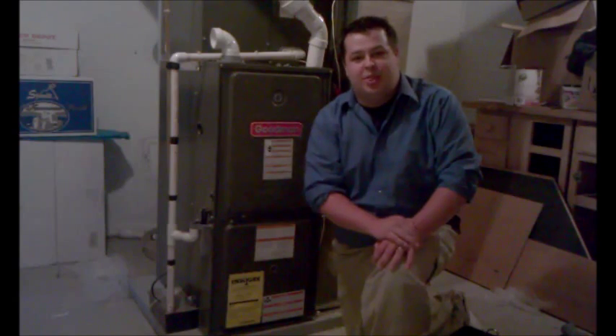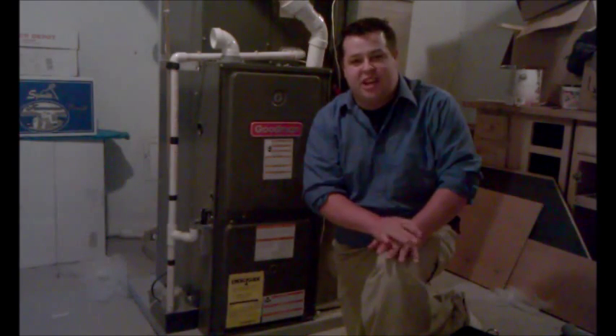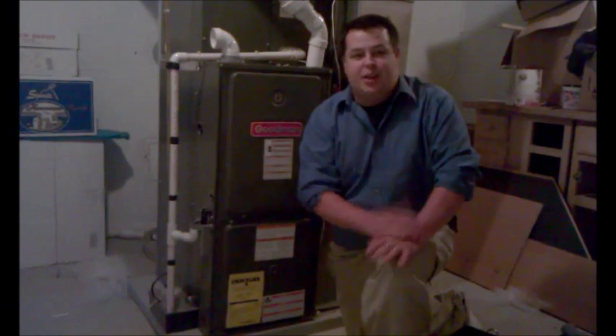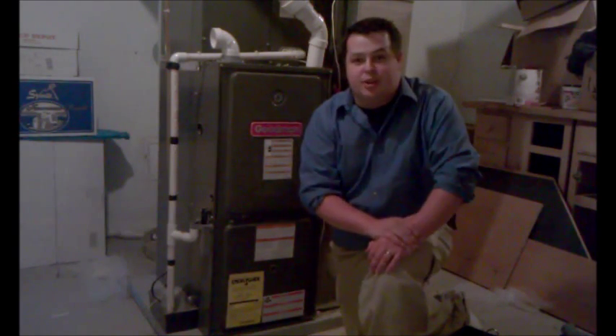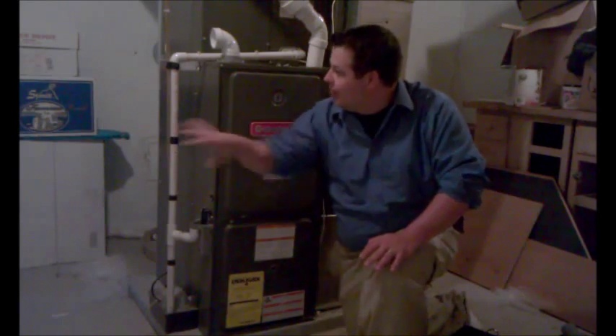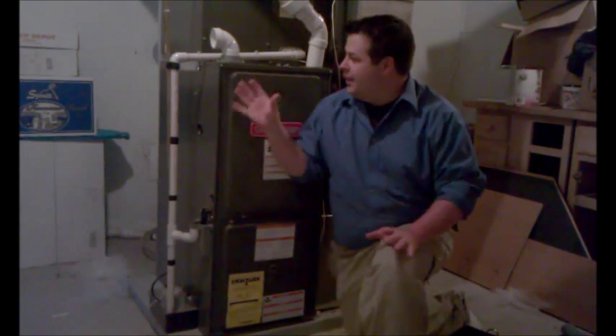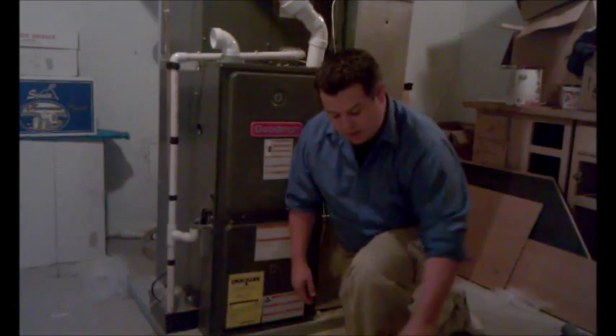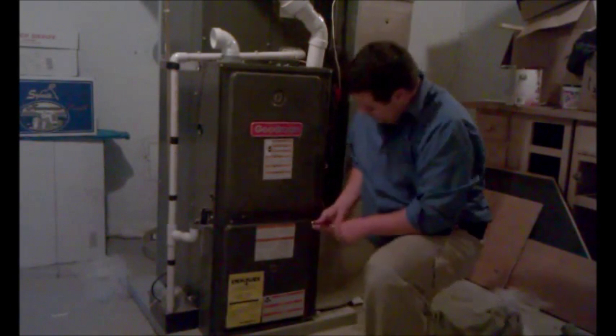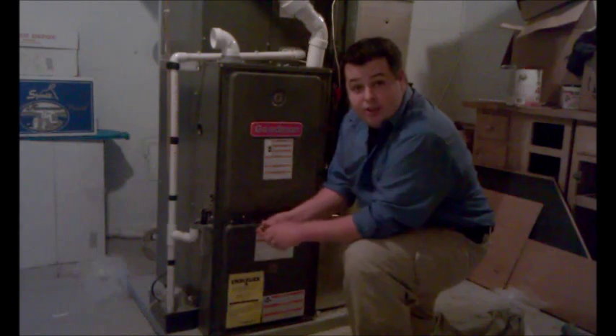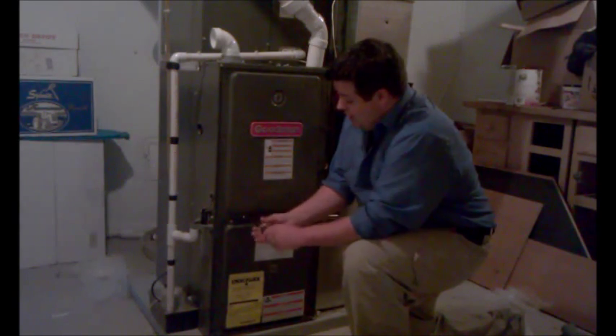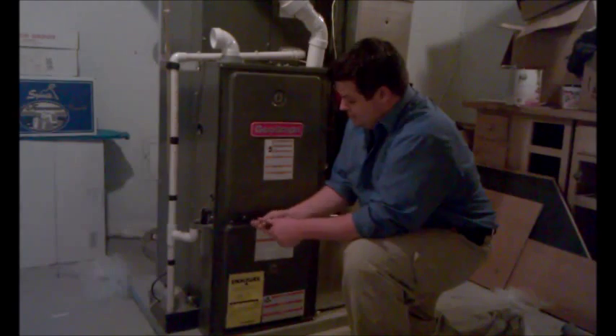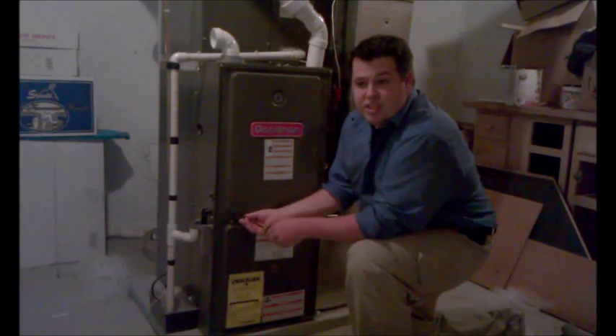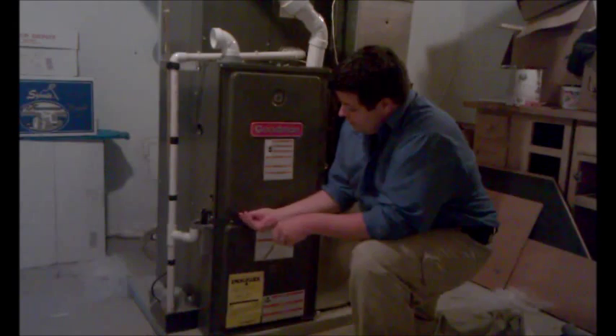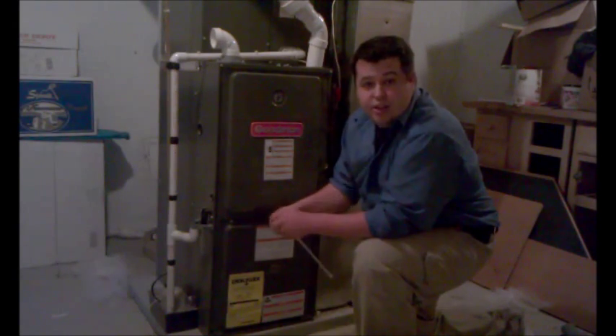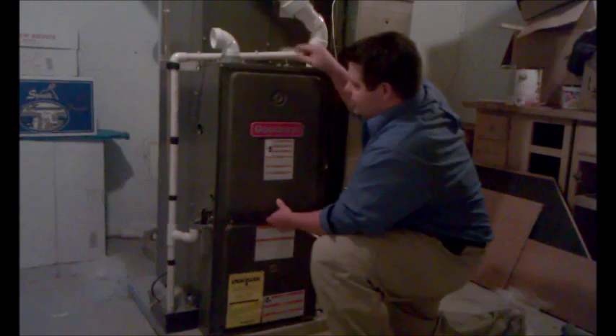I wanted to show you real quick what is involved in checking out your furnace. As you can see here, you're in my utility room. Looks probably very similar to what your utility room or closet looks like. It's got the water heater back there and everything. But anyway, I wanted to show you what is involved in a heat checkup when you're checking up your gas furnace. You may have an electric furnace, which we do very similar things, adjusting the airflow and making sure you're getting good efficiency out of the system, as we do with the gas furnace.